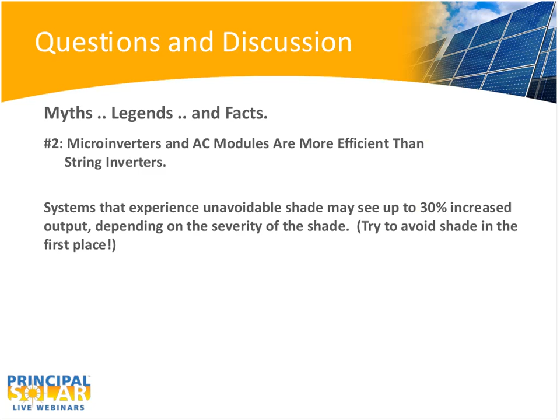The advantage to the microinverters is they all come out with grid-ready AC. Microinverters, whether they're AC modules already embedded into the photovoltaics or a microinverter that gets attached to the PV. And I want to make sure that you understand that distinction. There are companies out there that have attached microinverters to the PV, and they are being marketed as an AC module. If you look at NEC Section 690, by definition, all of DC wiring is considered enclosed, not visible.